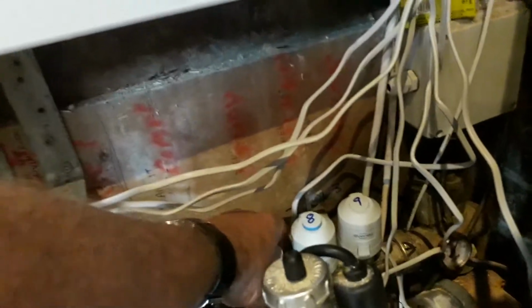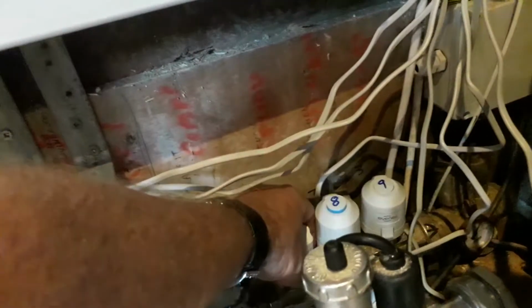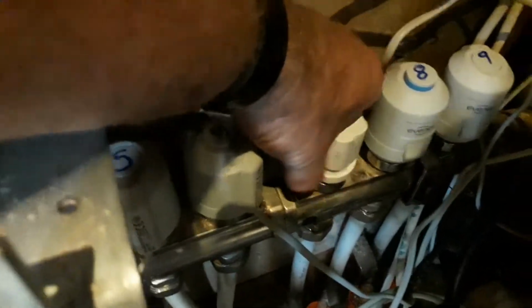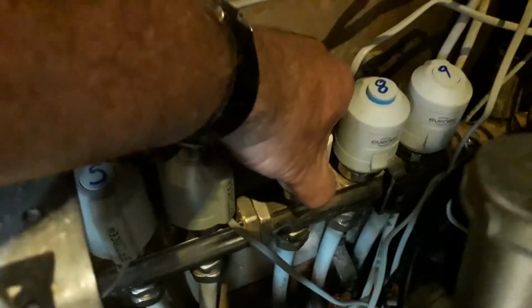This we just keep safely someplace where it won't get lost. And then we take one of these mechanical valves and we screw it on here to, in this instance, loop 7. We screw on the bottom piece just down there firstly, and that can be a little fiddly. If it's hard to thread it, then bring it backwards until it clicks in and then go forwards. And then when the little bottom piece is on, we screw this top piece down, and that shuts off the flow in loop 7.